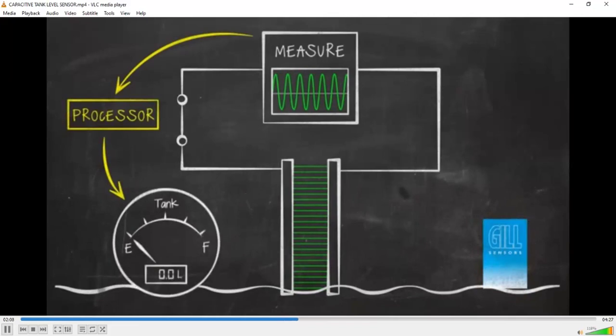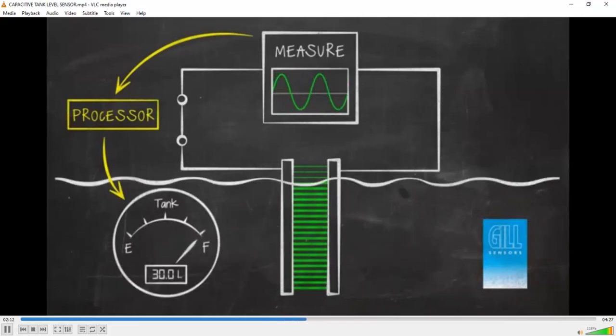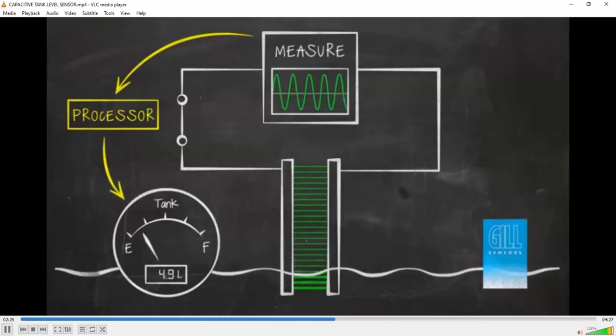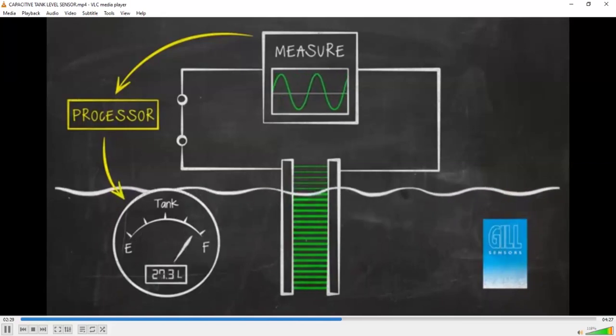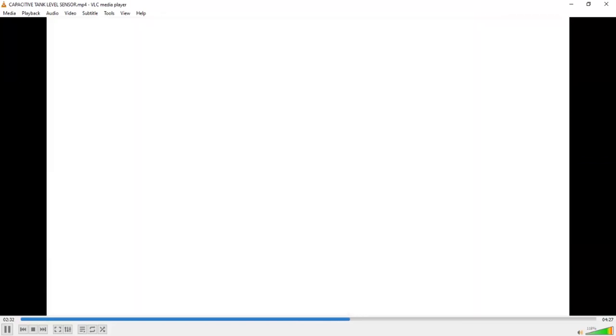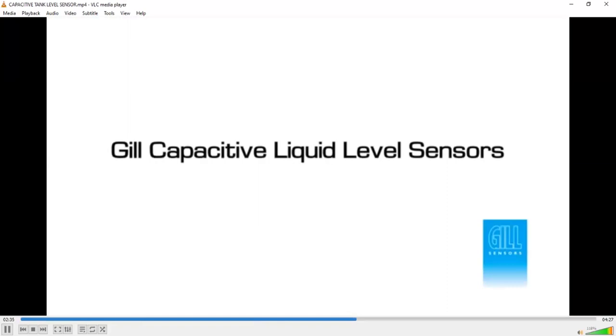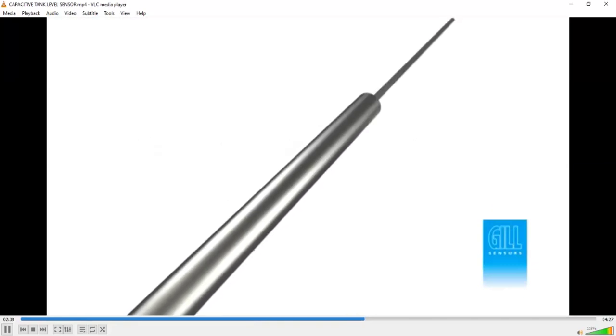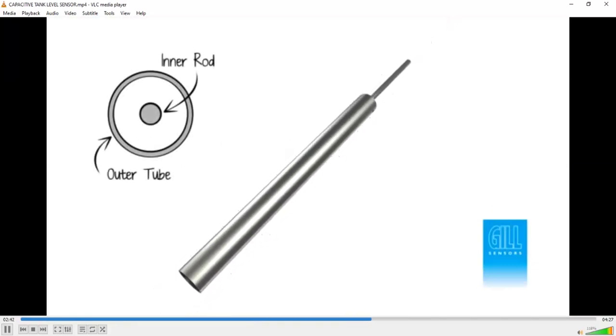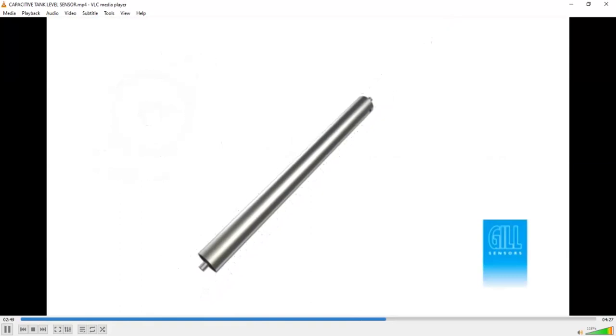For sensor calibration, reference measurements at empty and full tank conditions must be taken. Generally, we need to know the dielectric constant of the liquid being measured to calibrate the sensor at its full condition. With the empty and full outputs established, liquid level sensing comes down to relating sensor output to these values. Capacitor plates can also be deployed as concentric tubes, with the advantage of reduced interference, as well as improvements in mechanical stiffness and robustness. Fully integrated electronics mean no external electronic units are required, as all signal processing is managed on board.